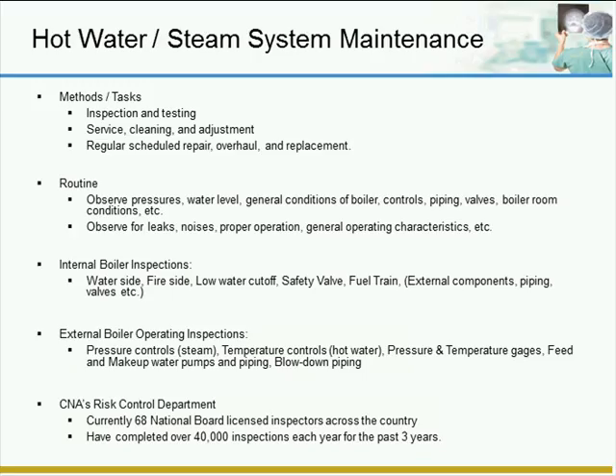Annual inspections include internal and external inspections. An internal inspection on a boiler consists of draining the boiler. The water side of the boiler will be inspected for scale buildup, blistering, pitting, and overall structural integrity. Preventing and reducing scale buildup will improve efficiency.